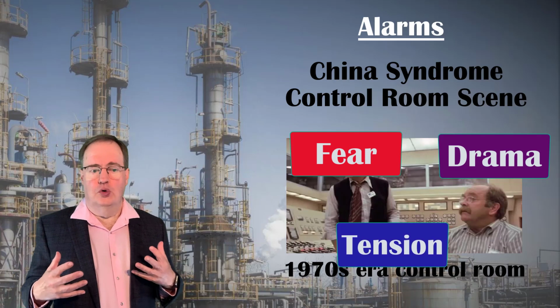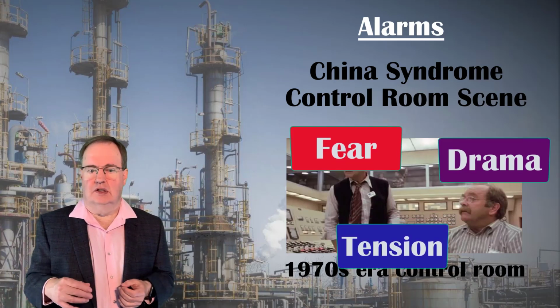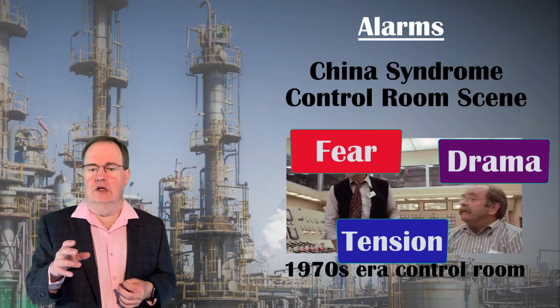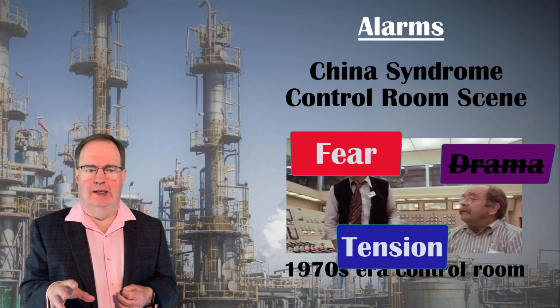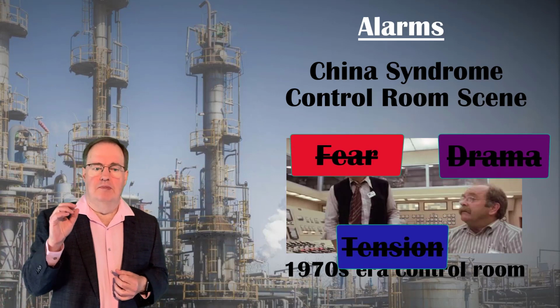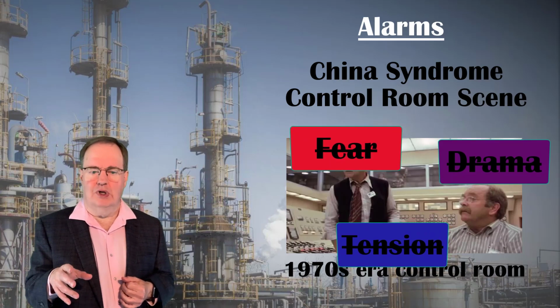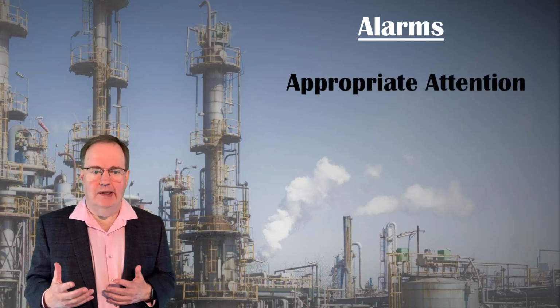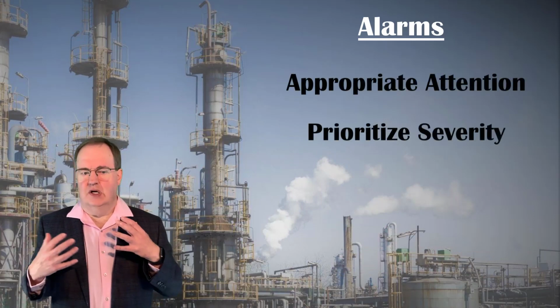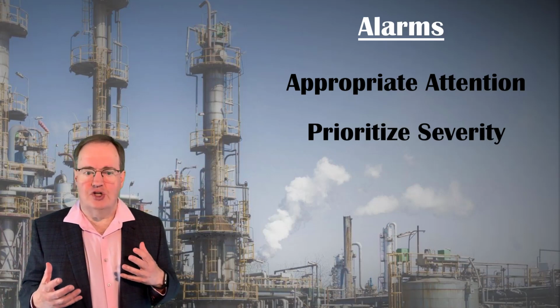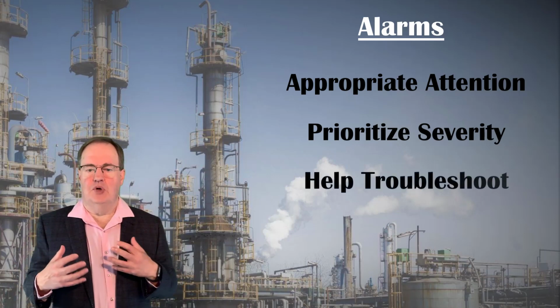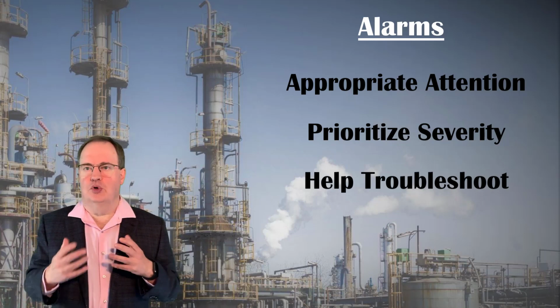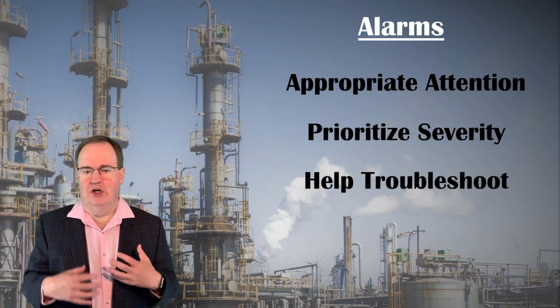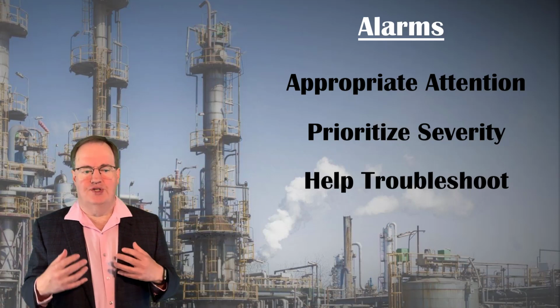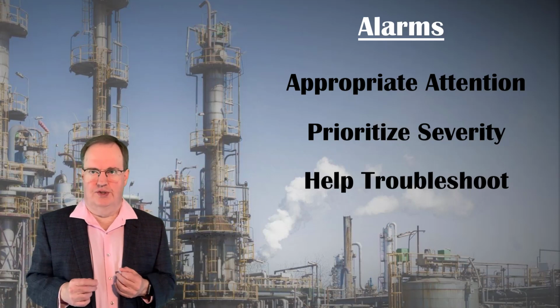In real control rooms without Jane Fonda and Michael Douglas, tension and fear are deeply undesirable. There are many alarms, most unimportant, triggering frequently. Alarms need to be noticed and dealt with calmly. Different levels of severity deserve different levels of attention. What we will talk about in this lecture is how to manage abnormal process situations, how to alert operators, and how to make it easier for those operators to succeed in managing those situations.